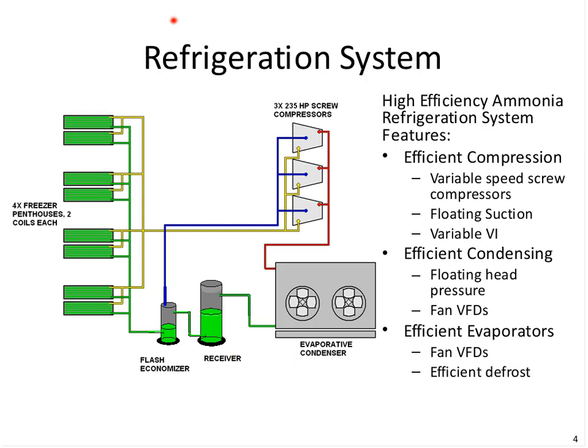On the next slide, here's a diagram of the refrigeration system. They're using the things we're going to talk about today. It's all standard equipment. We have high-efficient compressors, variable speed on those, and variable index, or VI. Floating suction pressure, we have efficient condensing, floating head pressure, variable frequency drives on the condensers, evap condensers, and we also have efficient evaporators.